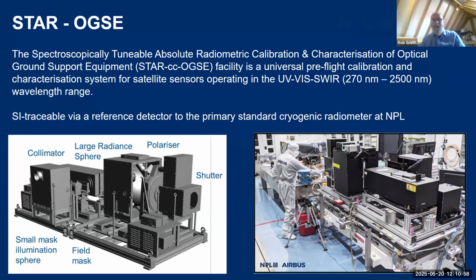So in the bottom right-hand corner there, you can see this system being used at an Airbus facility down in Toulouse, calibrating a satellite before it was launched a few years ago. Now, again, the engineering applications of this are complex, so we're having to take that reference measurement from our primary standard and find a way of transferring it over to a remote location. We're also having to build a system to comply with some very strict quality standards. So an ISO 5 clean room, for example, and with Airbus and ESA as our customers, we had to make sure we were able to interface with their quality systems and other requirements for the space industry.